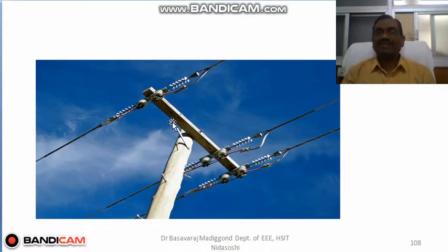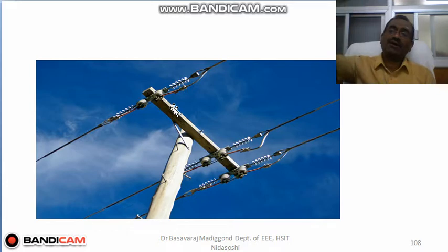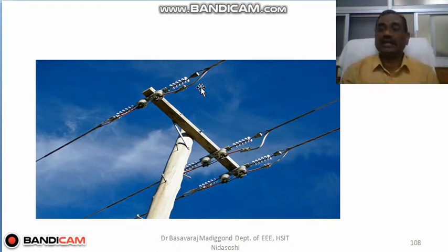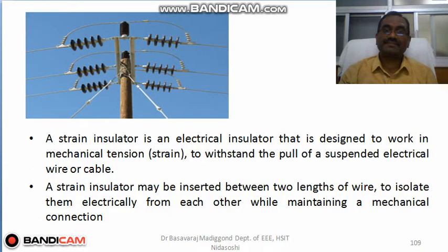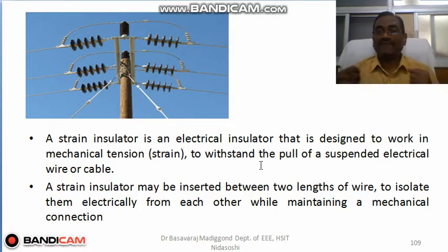See, the only difference is that in suspension type insulators, the insulators are suspended in a vertical plane, whereas these insulators are in a horizontal plane. If they are in a horizontal plane, they are called strain insulators. If they are in a vertical plane, they are called suspension type insulators. Okay? See, a strain insulator is an electrical insulator that is designed to work in mechanical tension to withstand the pull of a suspended electrical wire. Pull, see here, it's a pull.